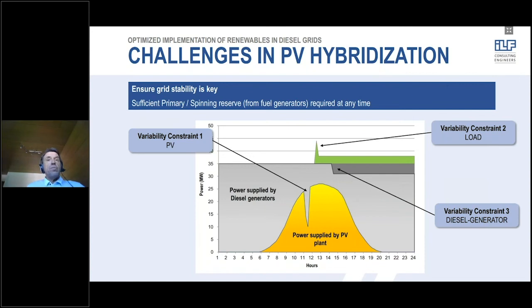We look, when planning, at main constraints such as a sudden cloud, which can reduce solar energy production by up to 80% within seconds. Another constraint may be the addition of a load, specifically a motor drive with high inrush current, or simply the breakdown of one diesel generator. When we check the grid stability, we even look at two such occurrences coming in at the same time.